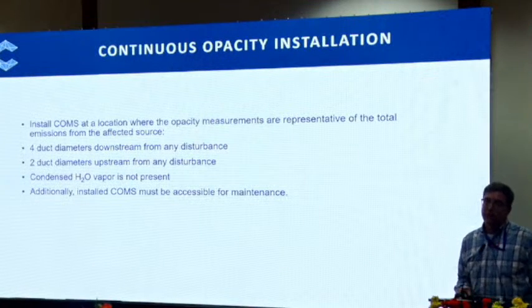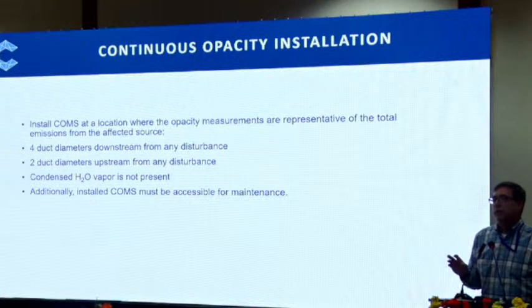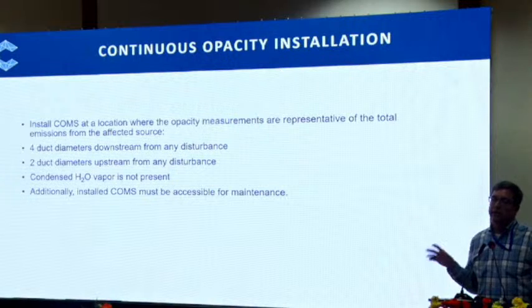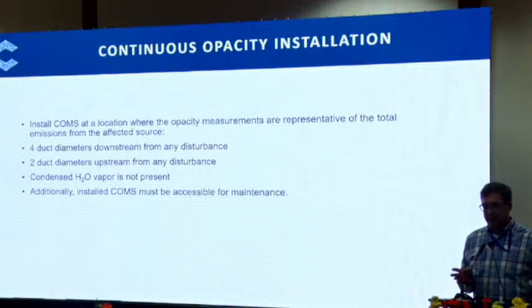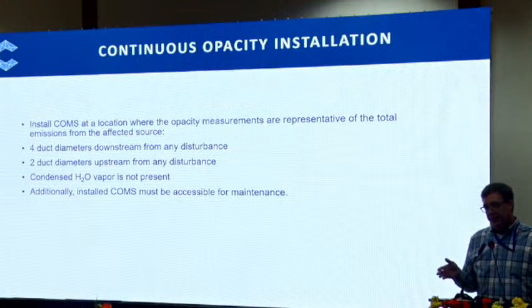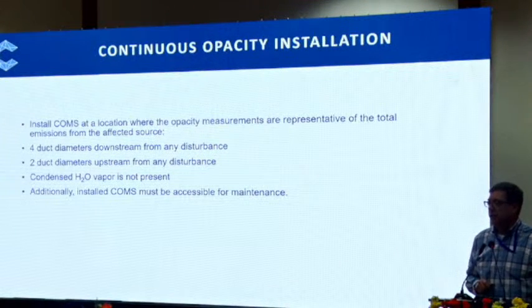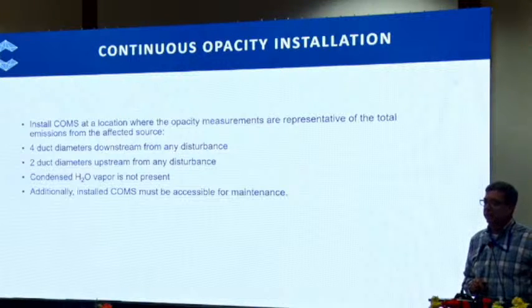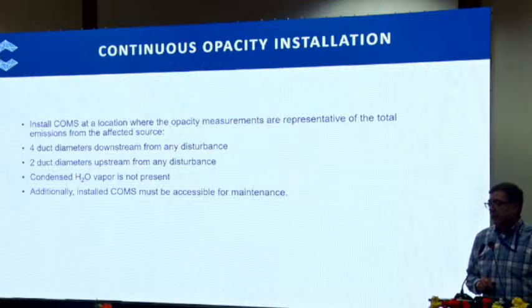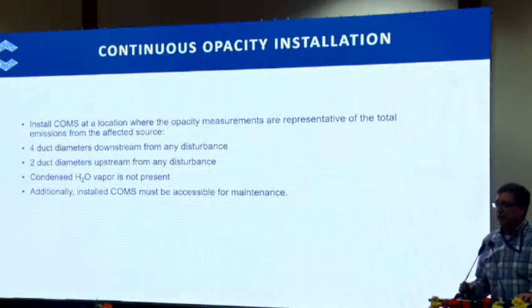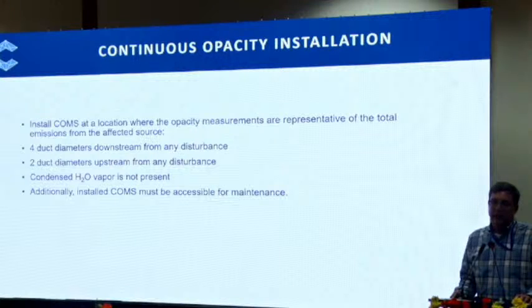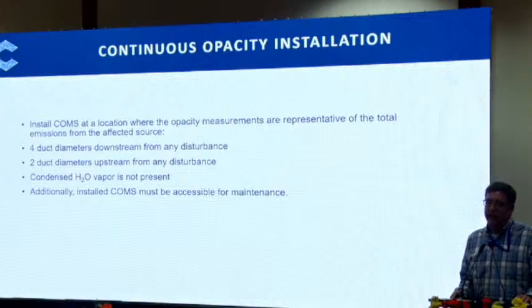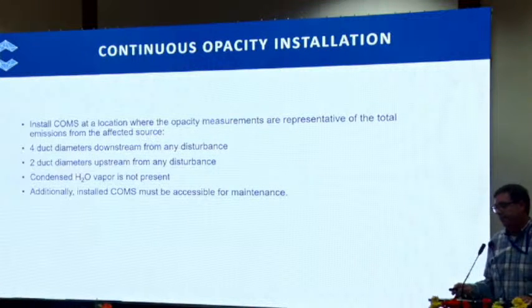Continuous opacity monitoring. In the United States, we take things a little bit differently. We don't typically measure opacity after an FGD. So if we have an FGD in place, we are required to have an opacity monitor between the dust control and the FGD. So we install the COMS at a location where the opacity measurements are representative of the total emissions from the affected source: 4 duct diameters downstream from any disturbance and 2 duct diameters upstream from any disturbance, and where the presence of condensed water vapor is not present. Additionally, installed COMS must be accessible for maintenance. The other thing is we use this on an opacity percentage. We don't try to correlate that with a mass rate.